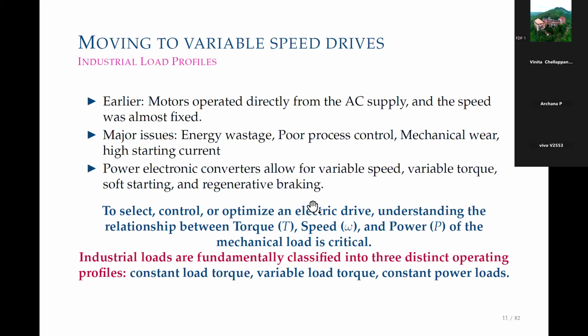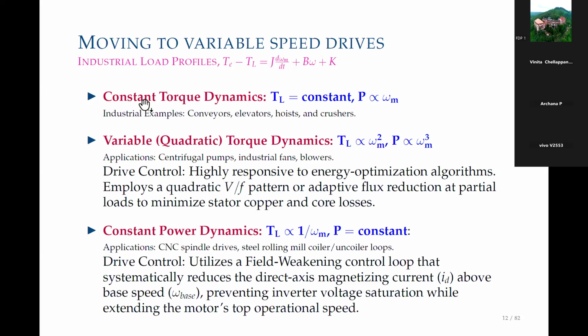But now, due to the advancement of power electronics, we are able to select, control and optimize an electric drive, and this can be optimized based on the load profiles available in the industrial sector as well as the EV sector. So we should understand the torque-speed relation as well as the power relation of the whole system, so as to select a motor or understand how we can control it. The different load profiles include constant torque load.